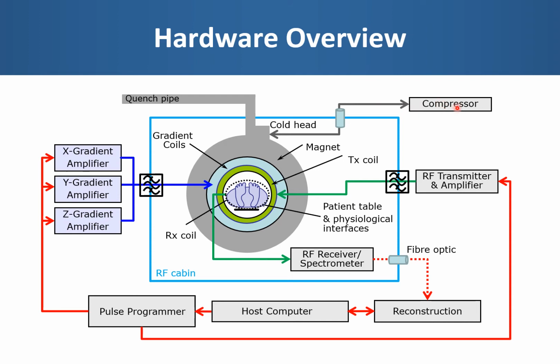Should the magnet ever cease to be superconducting, then the large amount of energy that is stored in the windings will be converted to heat. The liquid helium will be vaporized and will increase the pressure within the magnet. Again, there is a burst disc at the top here, which will rupture when the pressure exceeds a certain value, and then the helium vapor will be vented through the quench pipe to the outside of the building. This is important because helium can potentially asphyxiate people since it displaces oxygen, and it is also extremely cold.